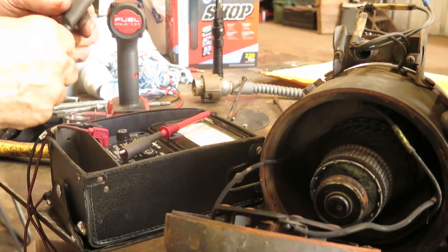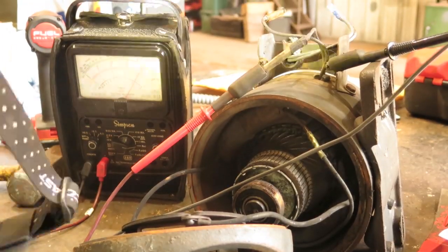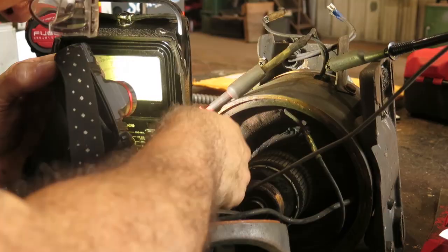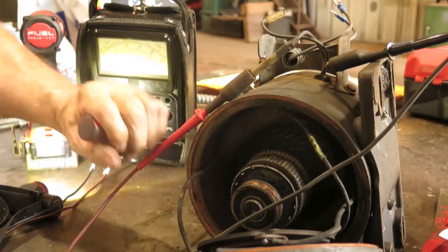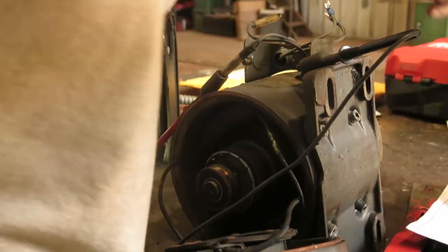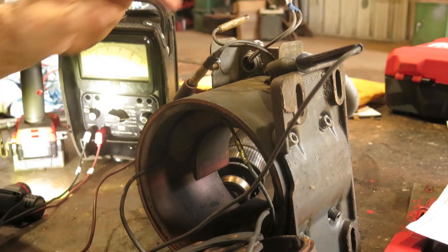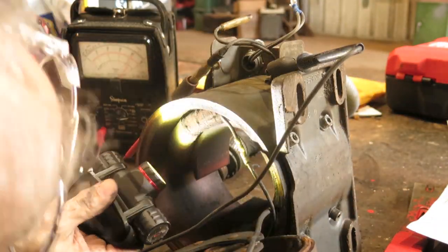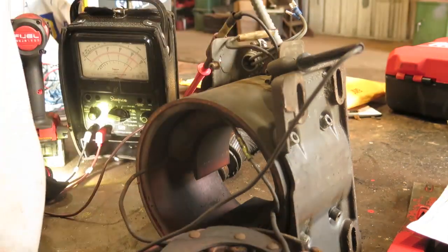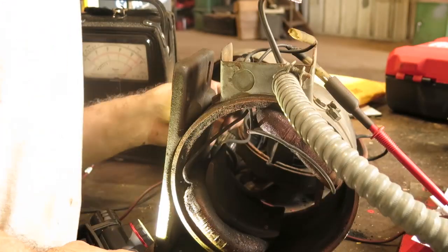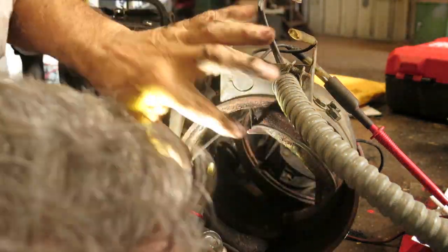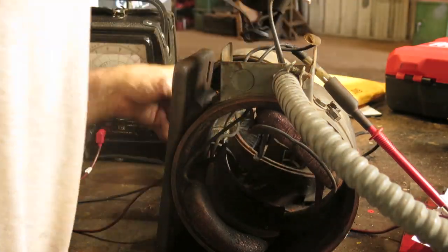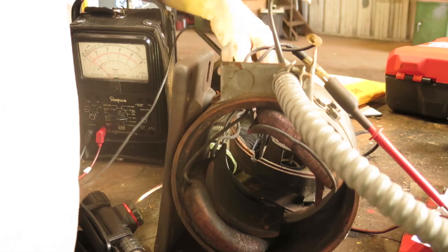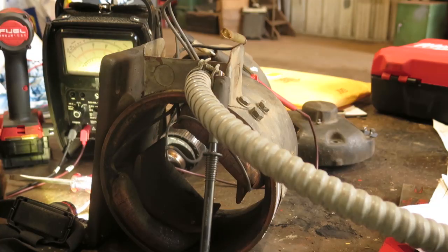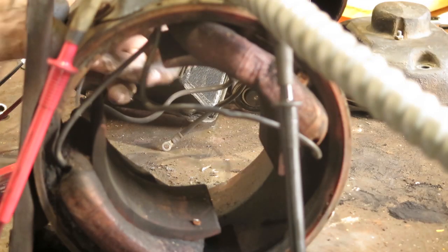With the brush holder end of the motor off, we're going to continue to keep checking for grounds and jiggling wires and seeing if anything changes. And if not, then we move on to the next step. Take the front end of the motor housing off, and that'll take the armature off with it, and then we'll look around and see if we can figure out if there's any other obvious problems, and go from there. Now I'm checking to see if there's any problems with the brush holder assembly, looking here, looking there, and not seeing anything. Went ahead and disconnected the brush holder assembly and set it aside, and we'll move on to the housing of the motor.